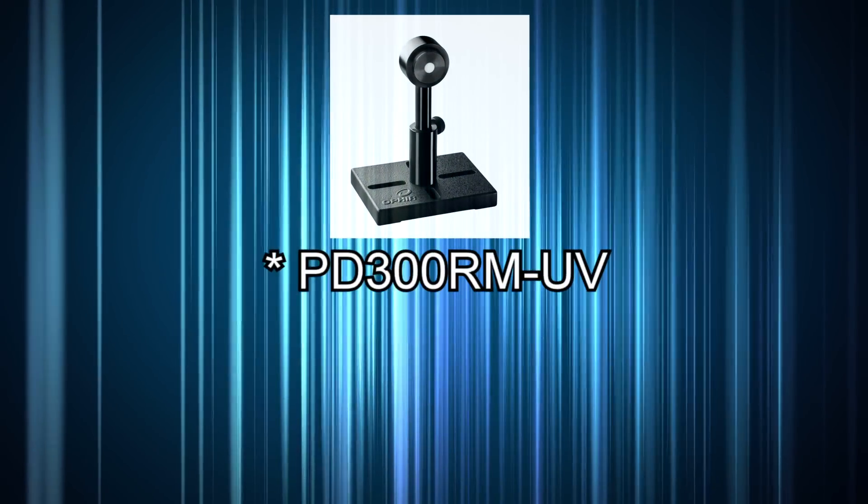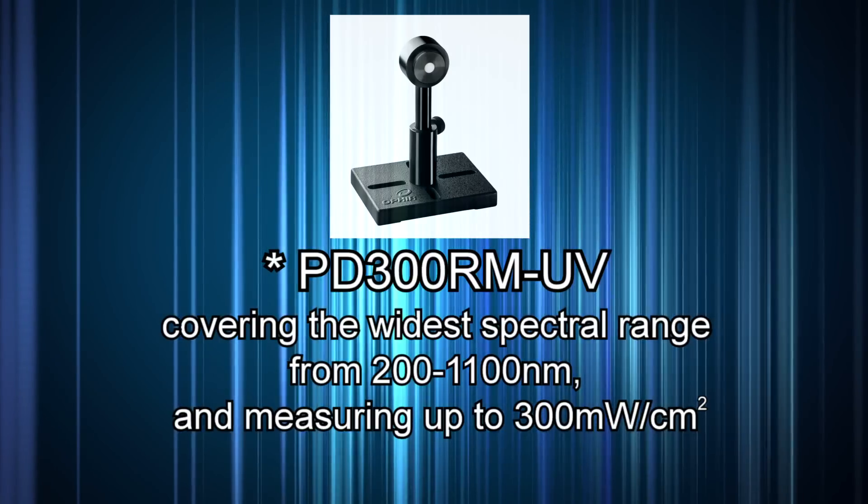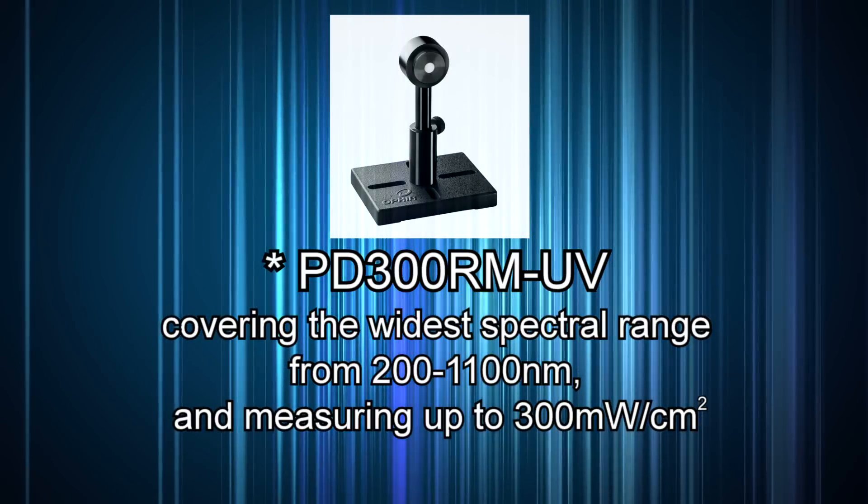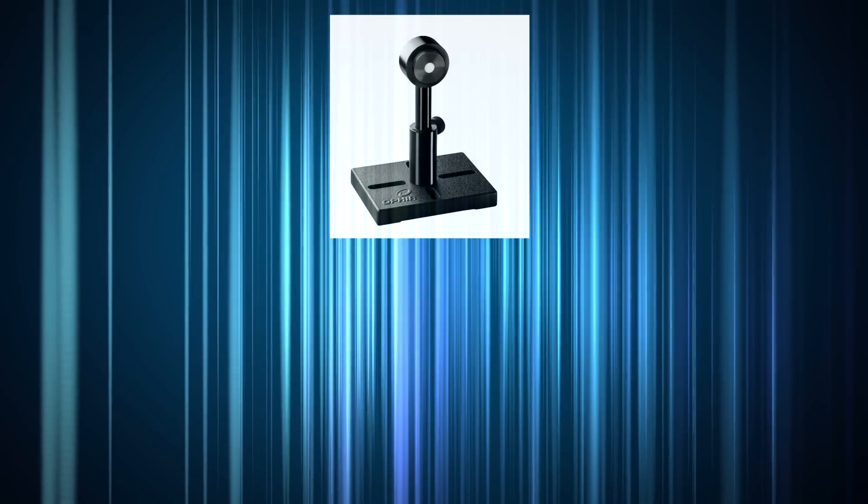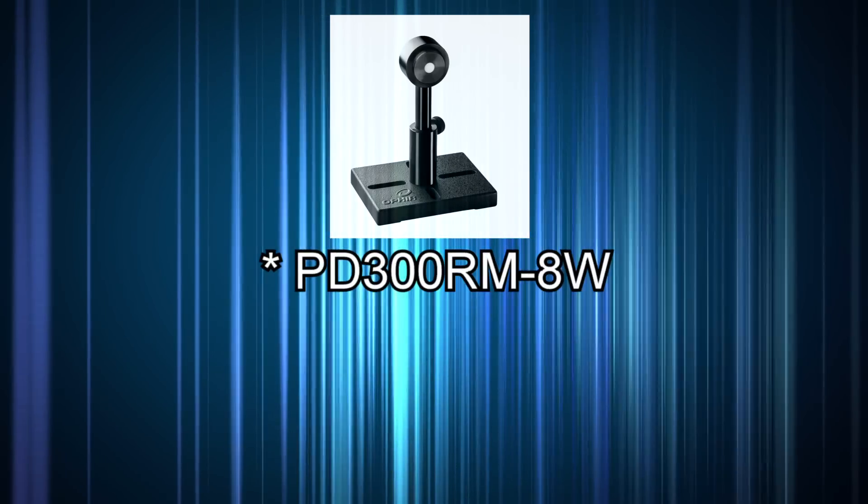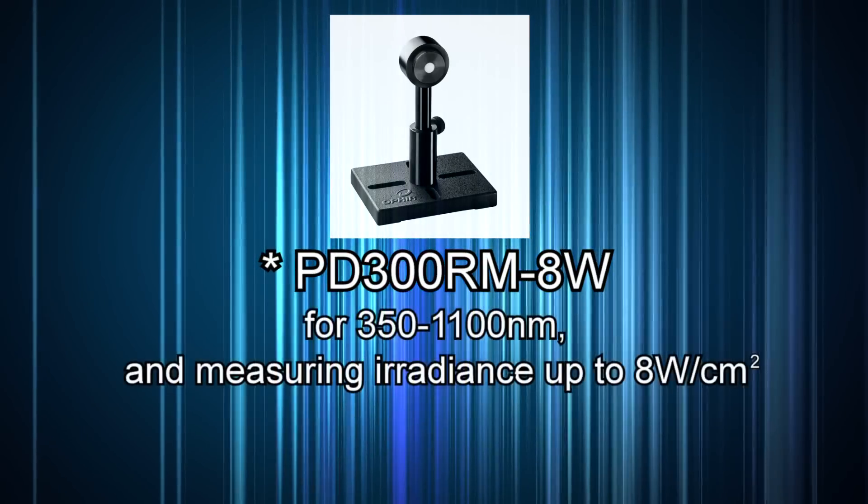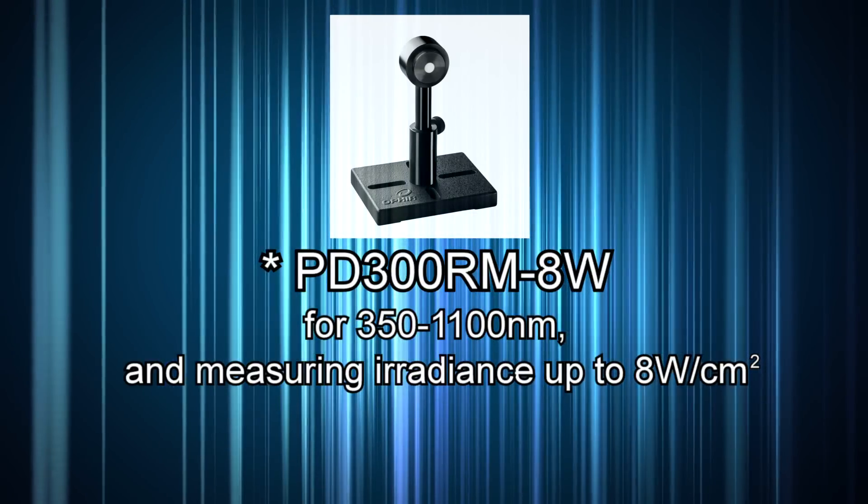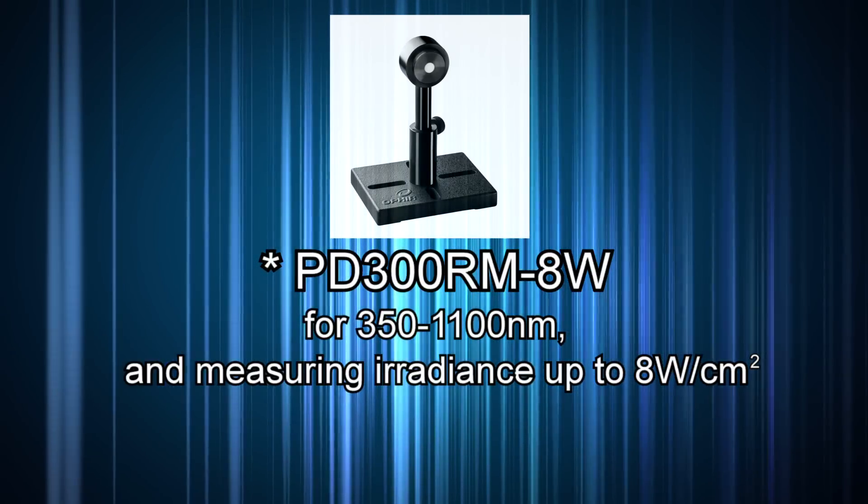There are two available models: PD300RM-UV covering the widest spectral range from 200 to 1100 nanometers and measuring up to 300 milliwatts per square centimeter. For higher powers, there's the PD300RM-8W for 350 to 1100 nanometers and measuring irradiance up to 8 watts per square centimeter.